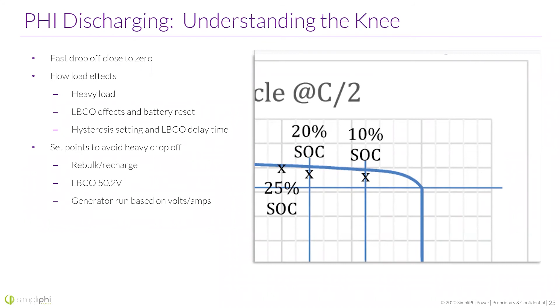A little bit about state of charge. Okay, let's just talk about this graph, or this little table here on the right. These are levels typically at C/2. This is what the state of charge relates to as far as voltage. This is just an estimate. Now, I will say this is done by our engineering team in a controlled environment. I'm going to tell you right now, I see much different in the real world versus what's controlled in the testing. For instance, 52.5 or higher is 100% state of charge. This is resting state of charge, which we're going to talk about in a second here. I don't see it that low. I see it typically in the field at about 53, 53.3.